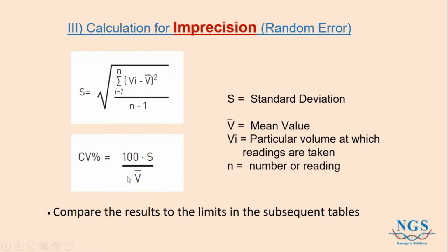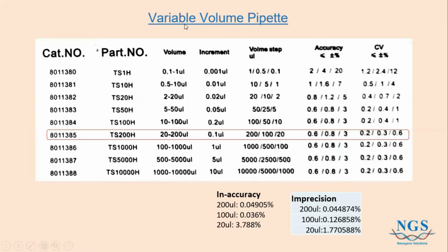At the end of it, you should have 3 inaccuracy values and 3 imprecision values. Once you have that, you can always compare your results to tables. Because I'm using a Top Science pipette, the manufacturer gives you a range of tables to see if your pipette is within the range, or to tell you where your pipette should be at. I was using a 20 to 200 microliter pipette. I checked the maximum value, which is 200 microliters, the 100 microliters, which is the 50%, and the smallest volume, which is 20 microliters. On the very back of the table, you see the accuracy range and the imprecision range for each of the testing volumes.